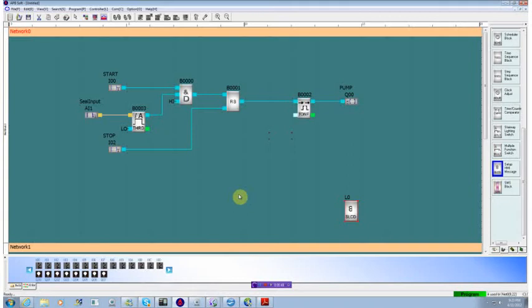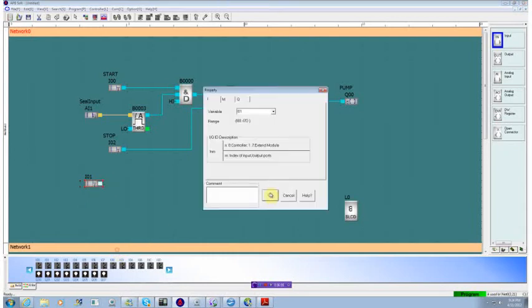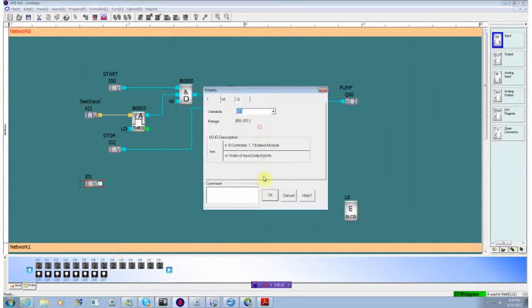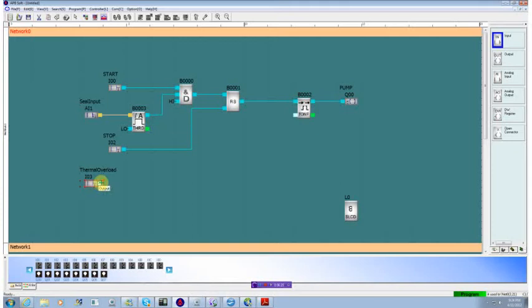The LCD screen block can be moved just about anywhere on the page. Well, the other thing we want to do is put in an alarm situation. Quite often a pump is going to have a thermal overload detect on it. So we'll tie in another input. We'll tie it to input number three. We'll call this thermal overload. It should be a normally closed contact coming off of a pump. And if it actually goes active, then we want to do two things. We want to immediately turn off a latch and relay, and we want to stop the timer.